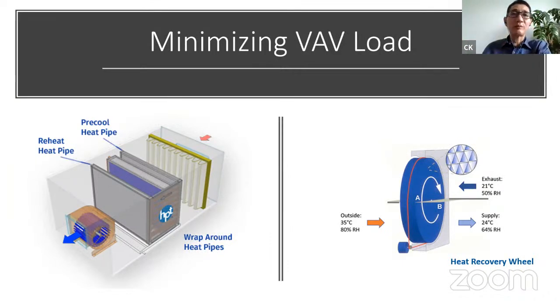To do that, we put in a wrap-around heat pipe around the AHU for the VAV system. The heat pipe will pre-cool the air, and then heat it back up. So the cooling in the VAV system is done mostly for dehumidification, removing moisture, and it reduces the cooling energy that goes into the VAV system. So that's the heat pipe.